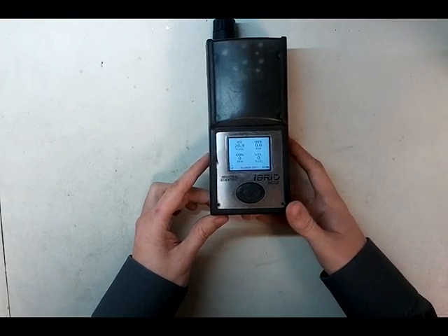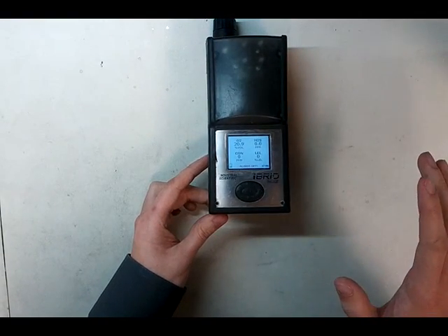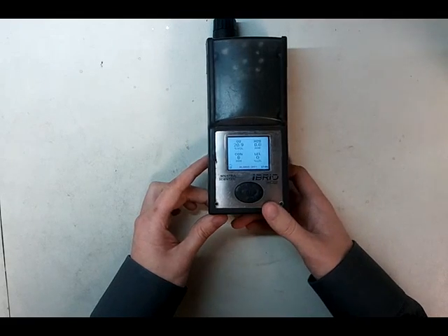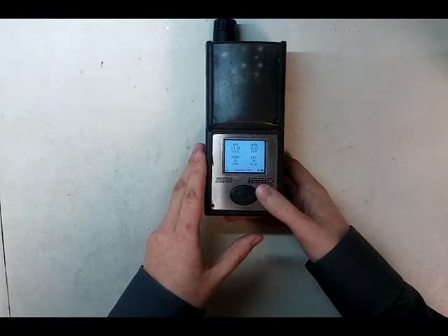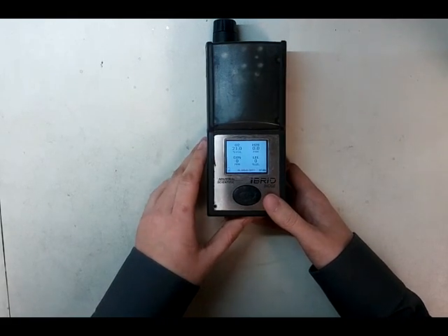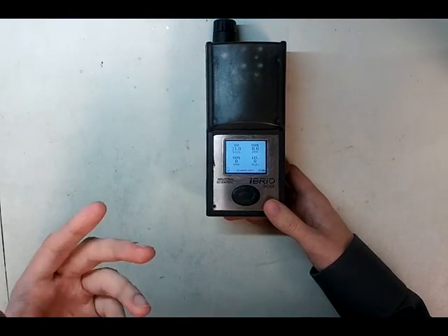Some companies out there recommend using pentane LEL as a calibration gas, and unfortunately what can happen is if the sensor is poisoned, it won't respond to methane when you go into a methane field or if there's a natural gas leak.